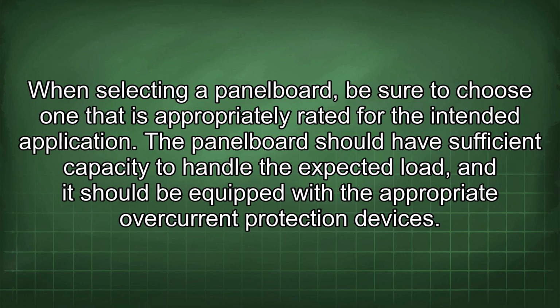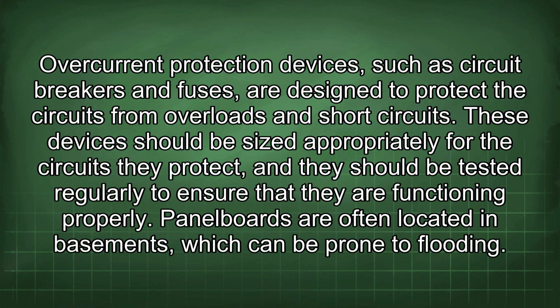When selecting a panel board, be sure to choose one that is appropriately rated for the intended application. The panel board should have sufficient capacity to handle the expected load, and it should be equipped with the appropriate overcurrent protection devices. Overcurrent protection devices, such as circuit breakers and fuses, are designed to protect the circuits from overloads and short circuits. These devices should be sized appropriately for the circuits they protect, and they should be tested regularly to ensure that they are functioning properly.